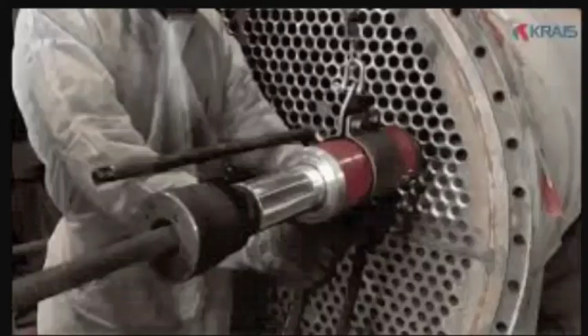Pulling out the eye bolt is normally outside that pressure zone, right? Yeah, outside the pressure zone. Okay, so then the thickness will not have an impact. I mean, if I calculate the thickness of the tube sheet, I should consider which is in the pressure and temperature zone. You can tell me if I am wrong, but that's normally how the calculation is done. Yeah, because we are calculating only for the number of holes. Yes.